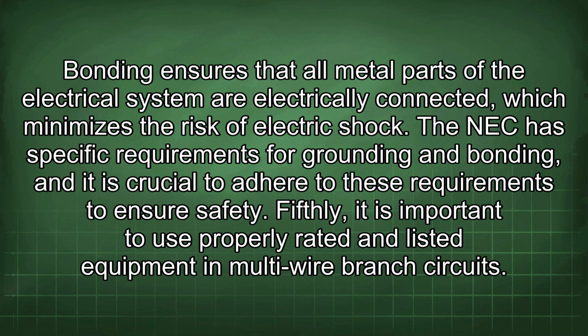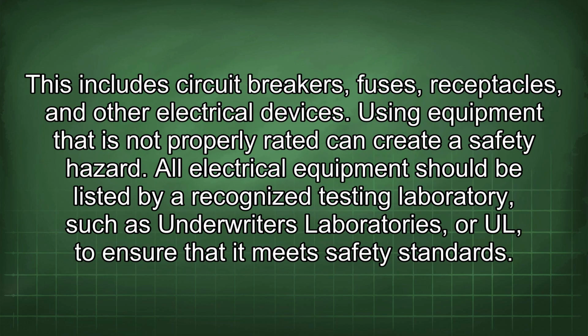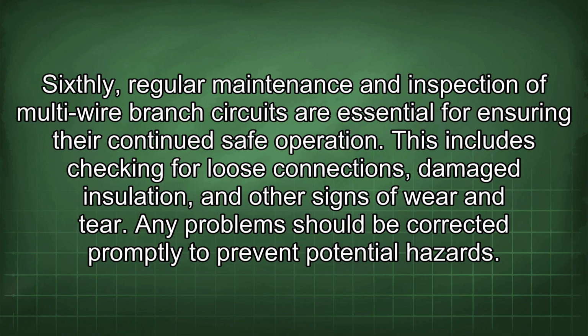Fifthly, it is important to use properly rated and listed equipment in multi-wire branch circuits. This includes circuit breakers, fuses, receptacles, and other electrical devices. Using equipment that is not properly rated can create a safety hazard. All electrical equipment should be listed by a recognized testing laboratory such as Underwriters Laboratories or UL, to ensure that it meets safety standards. Sixthly, regular maintenance and inspection of multi-wire branch circuits are essential for ensuring their continued safe operation. This includes checking for loose connections, damaged insulation, and other signs of wear and tear. Any problems should be corrected promptly to prevent potential hazards.